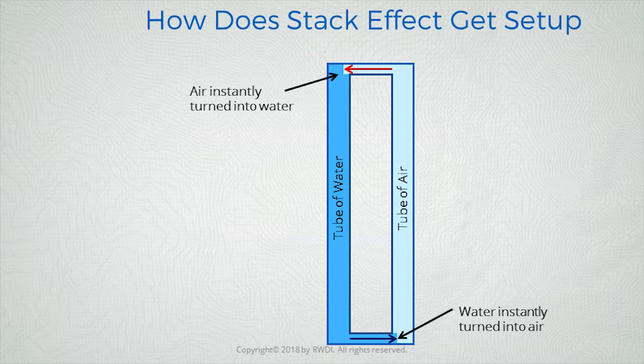So this process of cold air being turned into warm air on the inside of a building sets up the stack effect, and that's how buildings behave. So in this description, at no point have I said hot air rises. What I've said is it's about a pressure difference between the two.